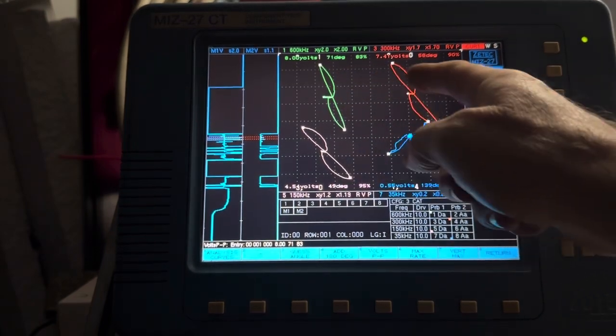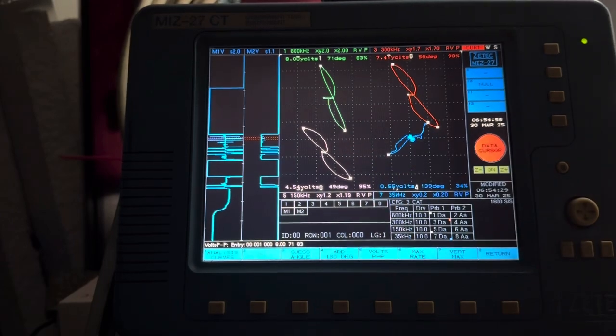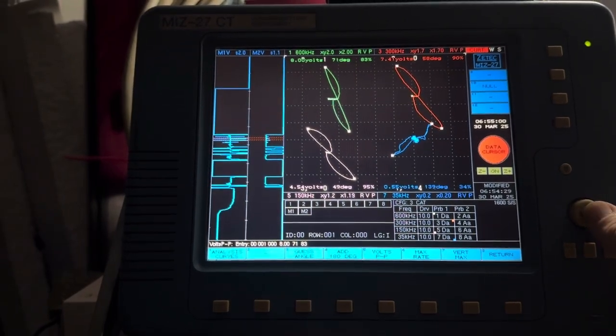71, lower frequency 58, lower frequency yet 49. So here we're looking at phase rotation. That's a big deal in terms of phase analysis. That's what we look for to determine depth of, at least for OD pits.